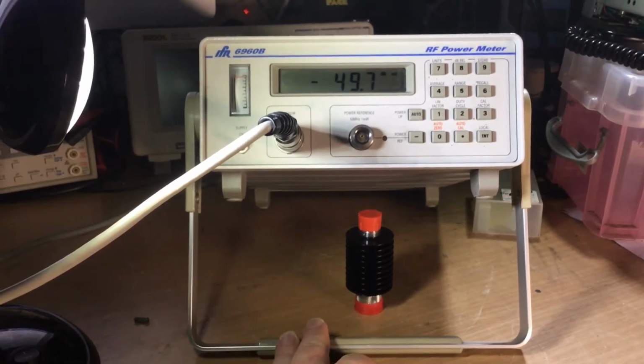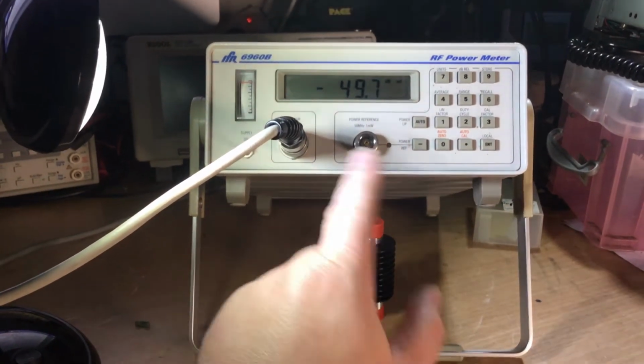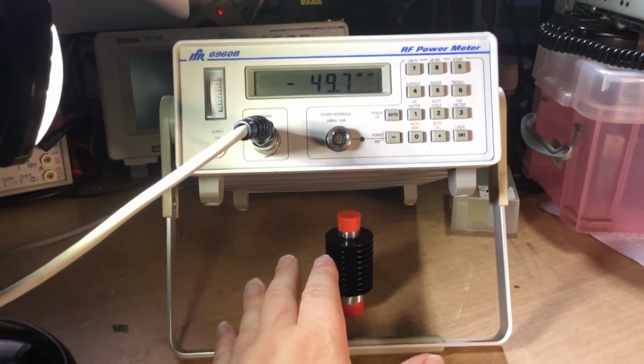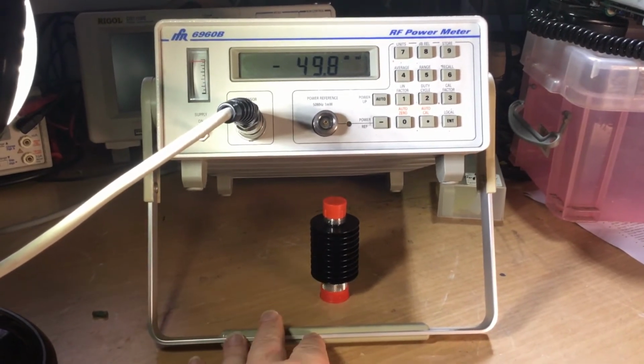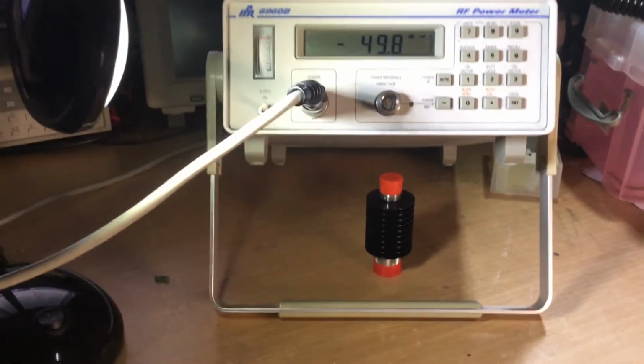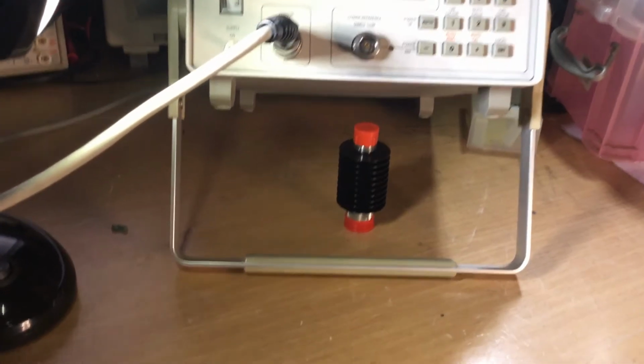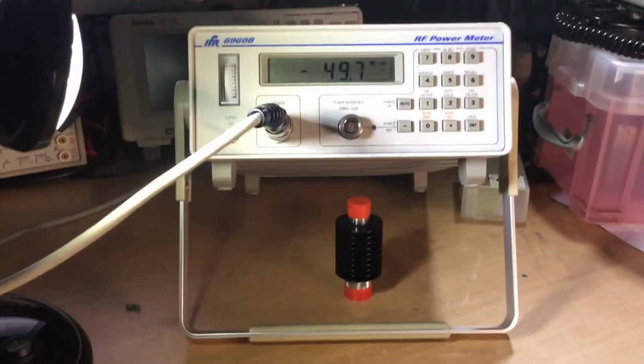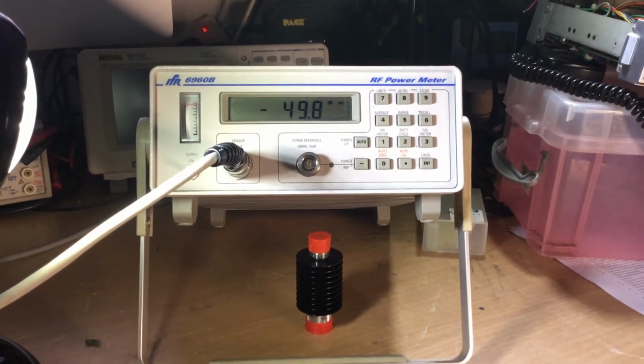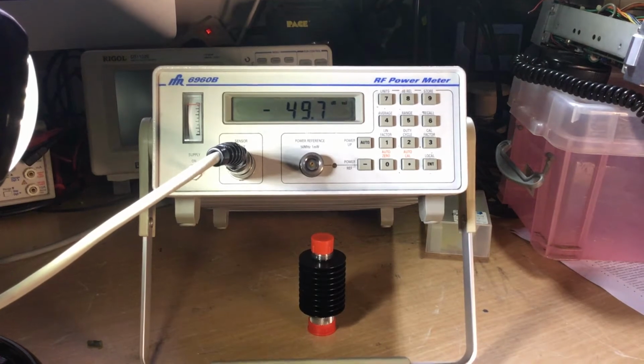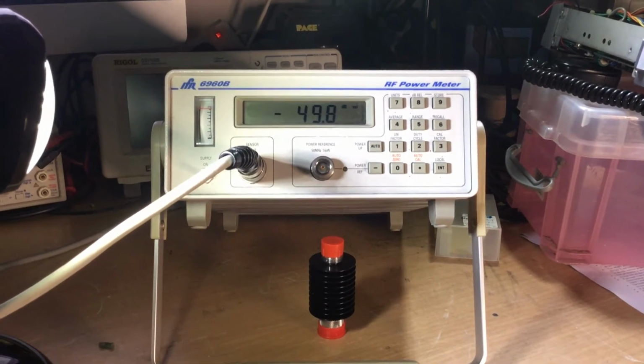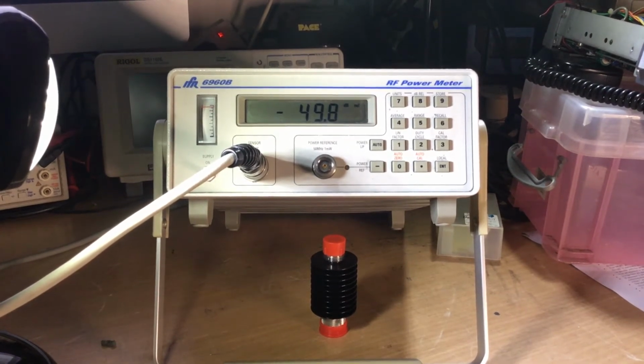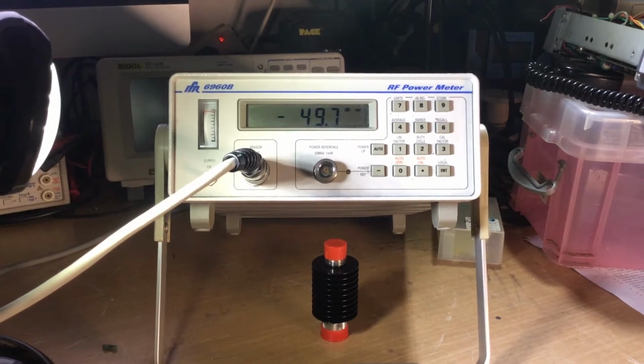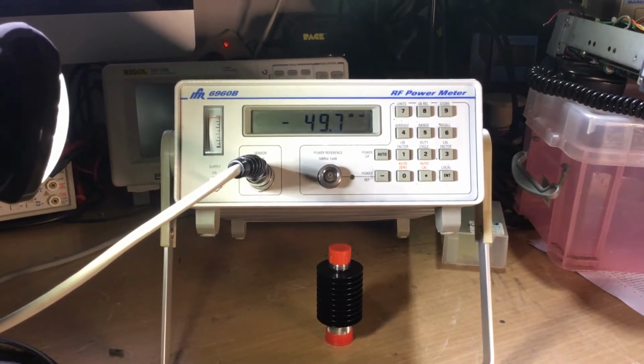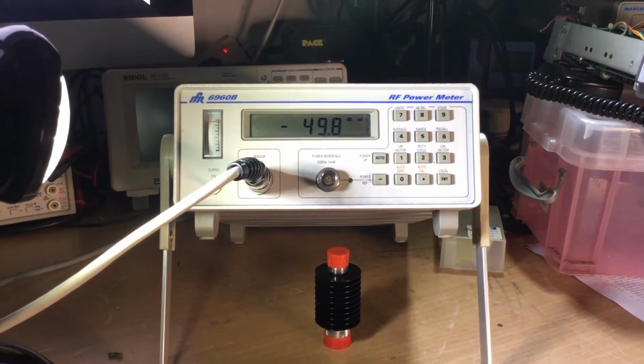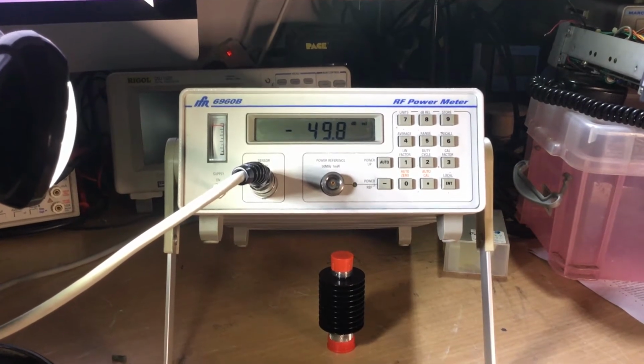So it's got two proportional voltage outputs, which is what I believe is on the rear panel, those BNCs we were looking at earlier. It says here two analog voltage outputs proportional to the RF input power are provided on the rear panel. The recorder output offers a full 50 dB dynamic range of the instrument in the dB mode at 1 volt per decade for wide range power measurements. In the watts mode, this output provides a 0 to 5 volt linear voltage proportional to the RF input power. The fast leveling output provides 1 volt per range for effective power leveling of sweepers or signal sources.